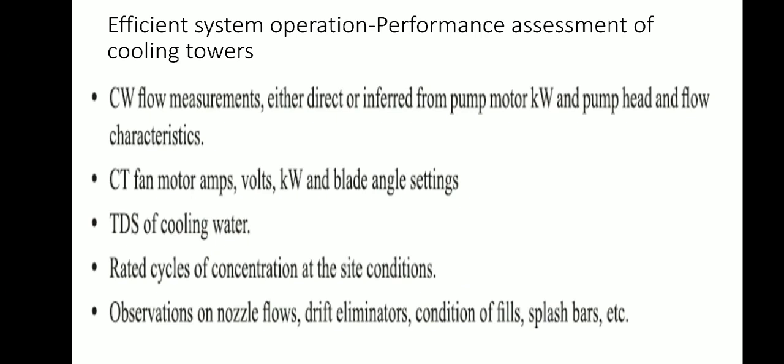Then cooling water flow measurement, either direct or inferred from pump motor kilowatt and pump head and flow characteristics. Cooling tower fan motor volts, kilowatt and blade angle settings. TDS of cooling water, rated cycle of concentration at the site conditions. Observations on nozzle flow, drift eliminators, conditions of fills, splash bars, etc.